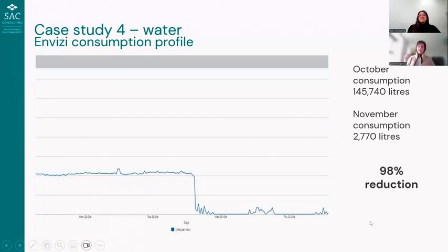Looking at the data again, just seeing what's going on in the shopping center, I noticed this small clothes shop had the same water consumption as some of the biggest restaurants we had in the shopping center. And I just thought, well, that can't be right. Surely there's something wrong with the data. But I noticed that it's always had that consumption, going back through the historical data.